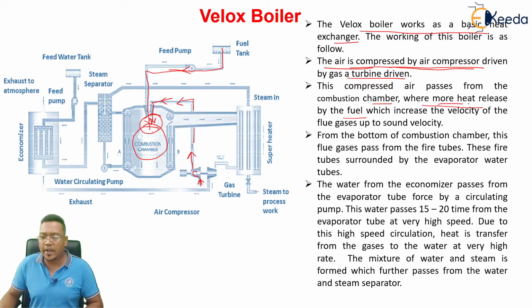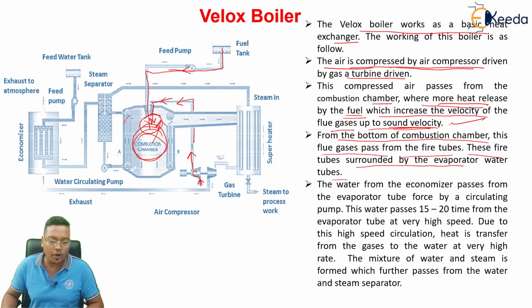Now, as more heat is released by the fuel, the velocity of the flue gas will increase up to the sound velocity. That means as more heat is released, the velocity of flue gas will increase, and it will increase up to the velocity of sound. Now from the bottom of the combustion chamber, the flue gas passes through the fire tubes. These fire tubes are surrounded by the evaporator water tubes. You see here, these are the water tubes and these are the fire tubes.